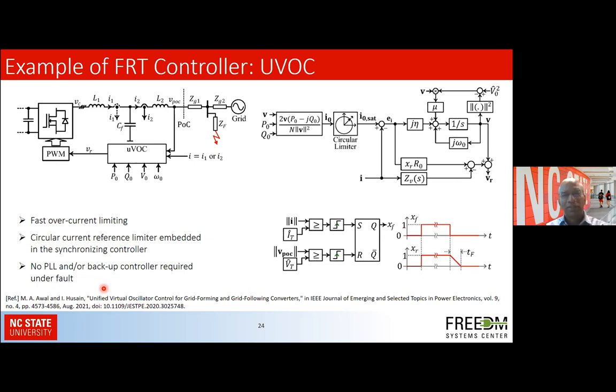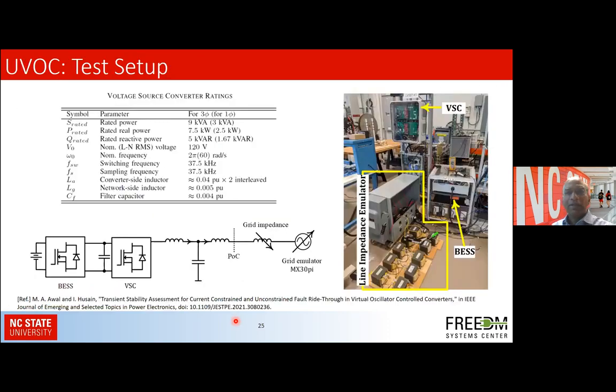So in this unified virtual oscillator control for grid forming and grid following converters, the key aspect of it is there is no PLL or backup controller required under fault. So this is a PLL-less controller, and we introduced a circular current limiter for current constrained operation under fault, and a fault has been simulated at the point of common coupling. And the hardware system, one of the test beds I showed earlier, has been used to validate the fault ride-through controllers using this hardware.